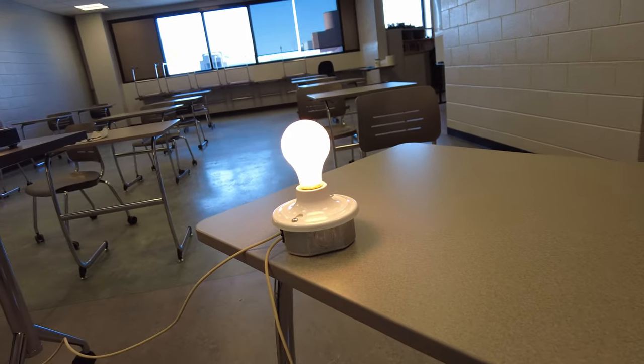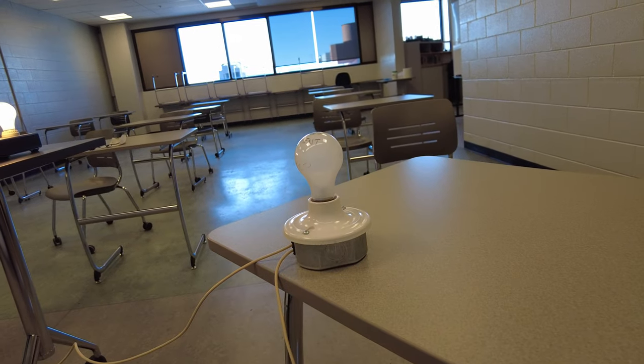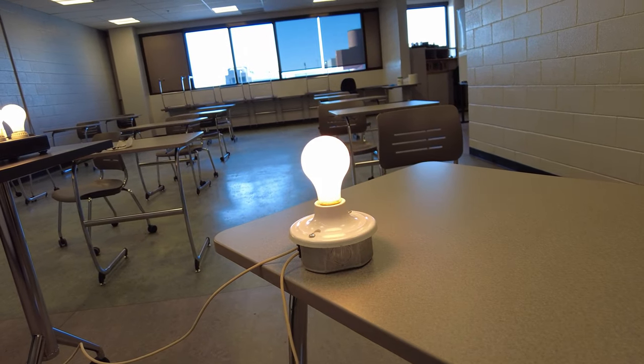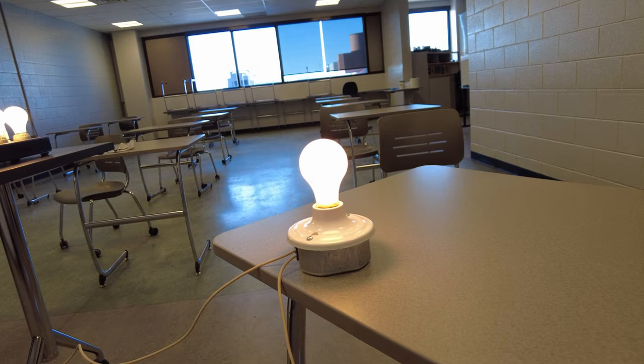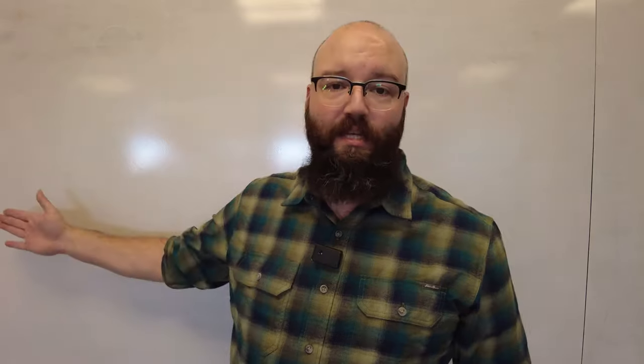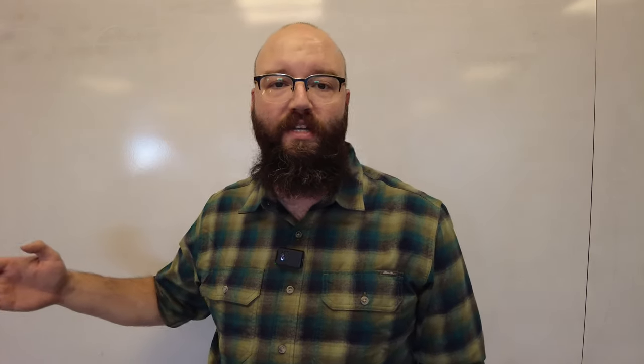Our light is now on, not touching the face plate, touching the face plate, not touching the face plate, touching the face plate. The danger in this situation is that light bulb could be an actual human being that's just touching something that's metal that has that potential imposed on it and something else out in the field that has a zero potential to it, that's also bonded back to that point where the neutral makes connection to everything metal.